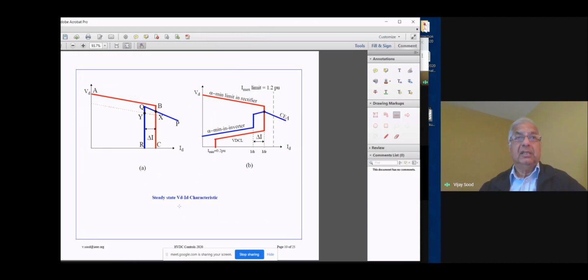For instance, let's say if this characteristic is something like this, the slope is quite steep over here, and that slope is a reflection of the commutation impedance at the inverter end. Now you can see the operating points will be X, there will be another operating point at this point over here, and then there's an operating point over there. So now you can have multiple operating points, and this can be a problem, especially when you have a weak AC system operating at the inverter end.